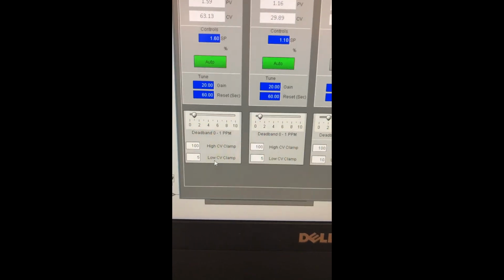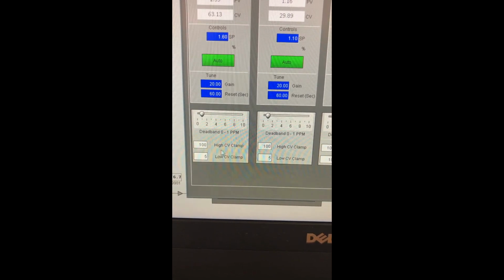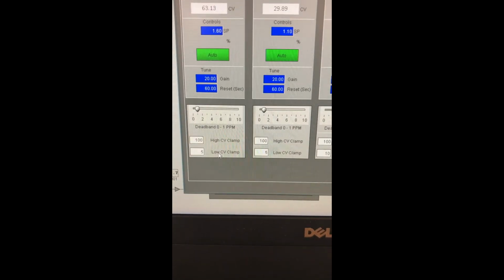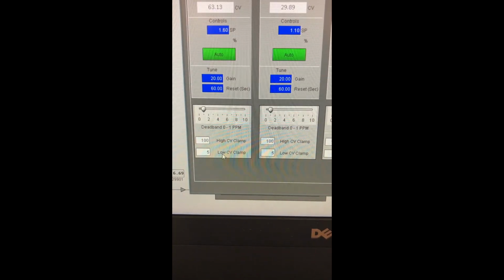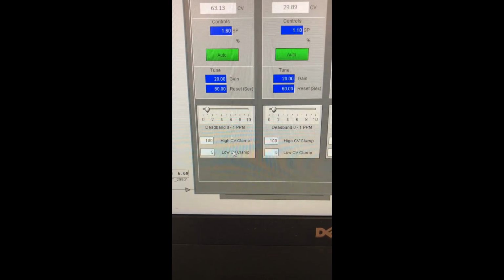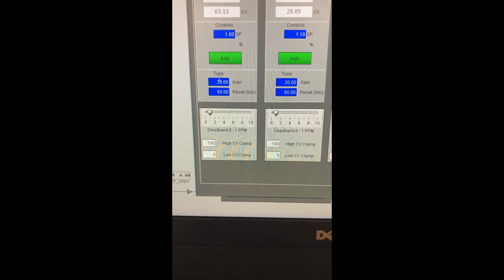And then we also have these low clamps. I've got a low control variable clamp that says never close the valve completely, even at low flow. Even if the DO starts to spike up when we have low flow, they can set that here. They can say that never close it more than 5%. So it'll always be at least 5% open.